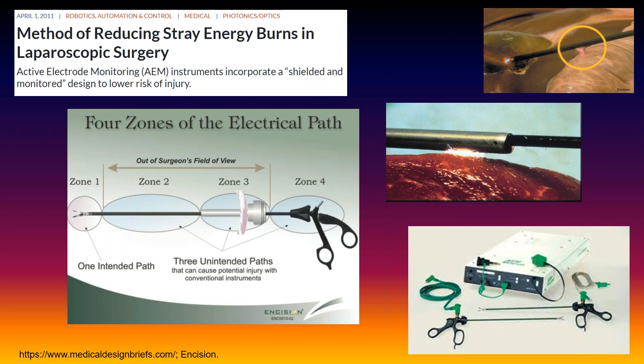What was even more tragic, they had a device for this. I don't know if any of you have these in your OR. They're kind of analogous to ground fault circuit interrupters, for electrosurgical units. They'll interrupt the machine if they detect a fault current like that. They had that machine on the cart with the ESU, but they didn't use it for some reason, because the OR record showed that it was on the cart. Had they used it for what it was intended for, it would have been all right.